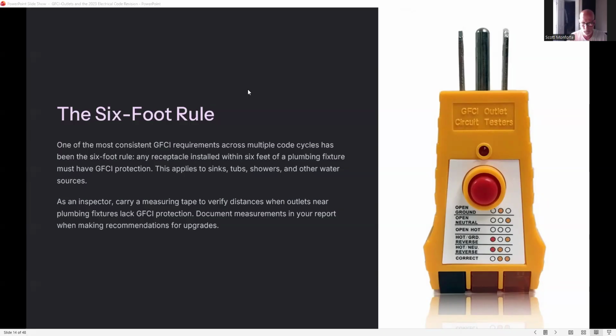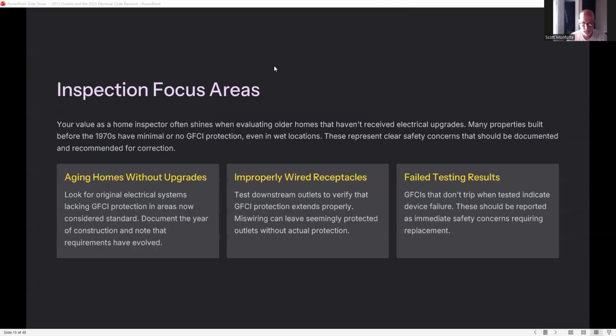Basically, this is a little outdated. Like we just talked about, all the outlets in a kitchen, in a bathroom, in the crawl space, in the basement really should be upgraded to GFCI protection. Inspection focus areas. Your value as a home inspector often shines when evaluating older homes that haven't received electrical upgrades. Many properties built before 1970 have minimal or no GFCI protection, even in wet locations. These represent clear safety concerns that should be documented and recommended for correction.